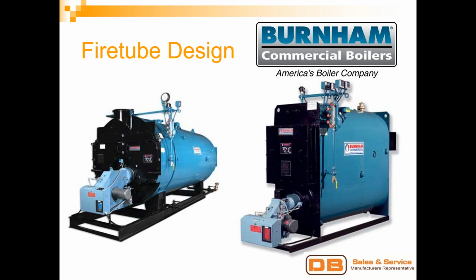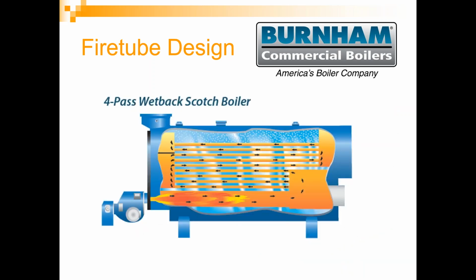They make both a compact version, as shown there on the right, as well as the traditional Scotch Marine shown on the left. And the Firetube boiler wasn't rocket science when they decided to come up with the name Firetube boiler. The fire actually travels down through the furnace, which in a Firetube boiler is typically water-cooled, down around through the multiple passes and through the tubes.